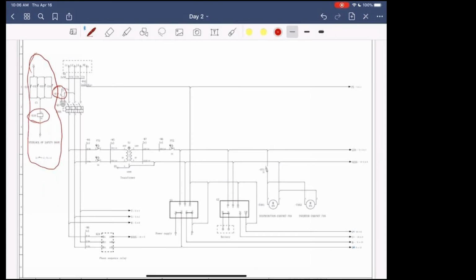So if you open a door, the solenoid kicks out, K18 will then go from normally closed to a normally open. When it opens up, it breaks the signal going into the disconnect. Therefore, it'll de-energize the disconnect and it'll kick out the breaker. So any of these switches which are on your doors are opened, it'll kick out again K18, which is a relay, which is controlled with this contact right here. So if that loses power, then everything will die. The shunt breaker will trip the breaker itself, and the power will be lost on the machine.